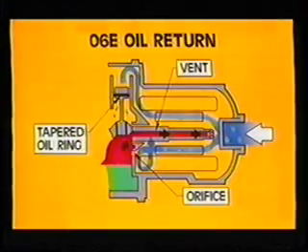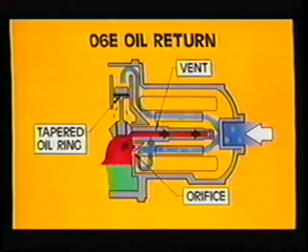The O6E compressor internal oil return system differs from the O6D design. As mentioned earlier, the O6E compressors are considerably larger than the O6Ds. However, the motor housings are the same diameter. Although the volume of the motor housing is the same for O6E and O6Ds, the volume compared to the O6E displacement is much smaller than for the O6D. More gas must move through the same volume. Therefore, the gas velocity in an O6E motor housing will be high.